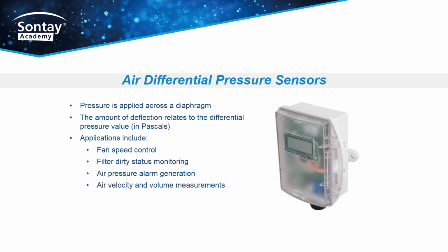Although not covered here in great detail, air DP sensors can be used to calculate air velocity and volume. Using a suitable probe in the air duct, a differential pressure measurement is taken between the total duct pressure and the duct static pressure. The resultant differential reading is the velocity pressure, which can then be passed to an equation to calculate velocity in meters per second. By multiplying this value by the cross-sectional area of the duct, measured in meters squared, the flow volume can be ascertained in meters cubed per second.